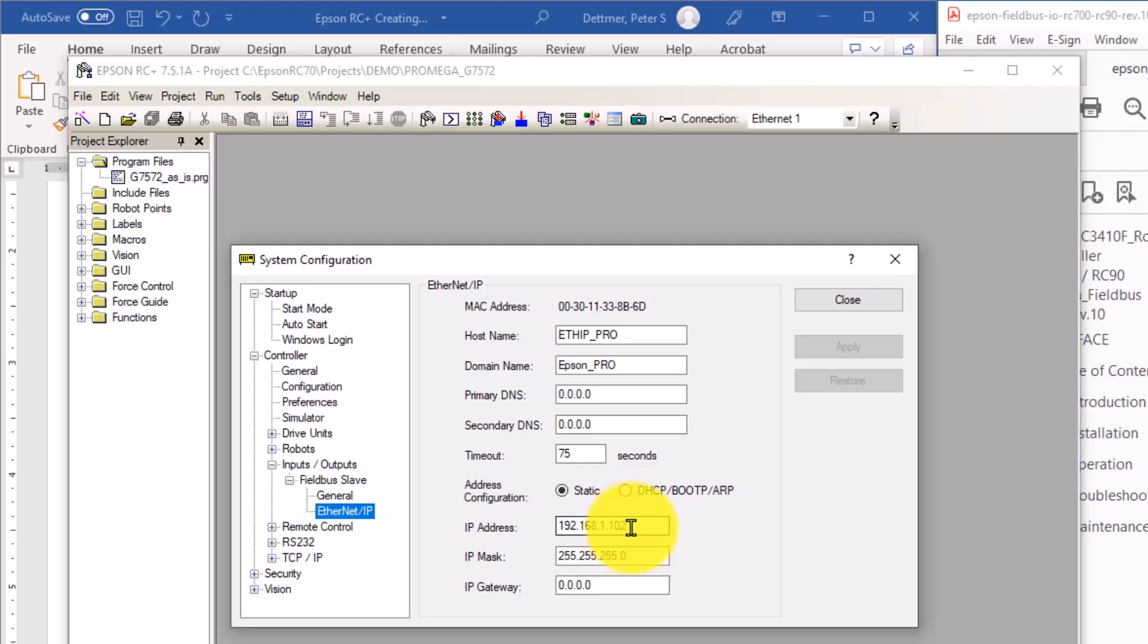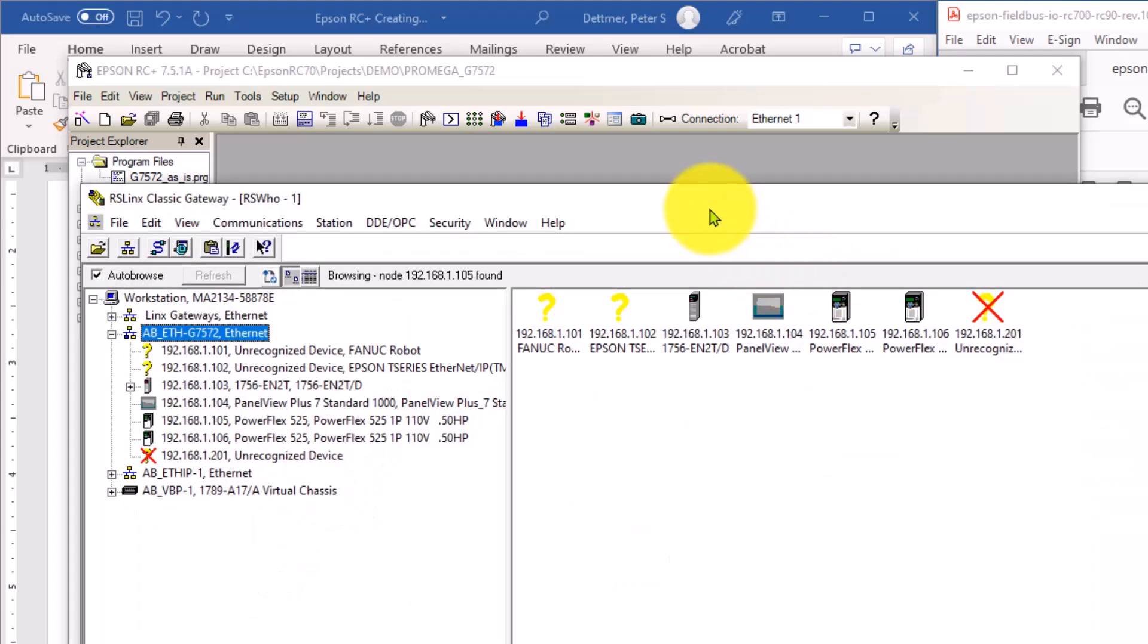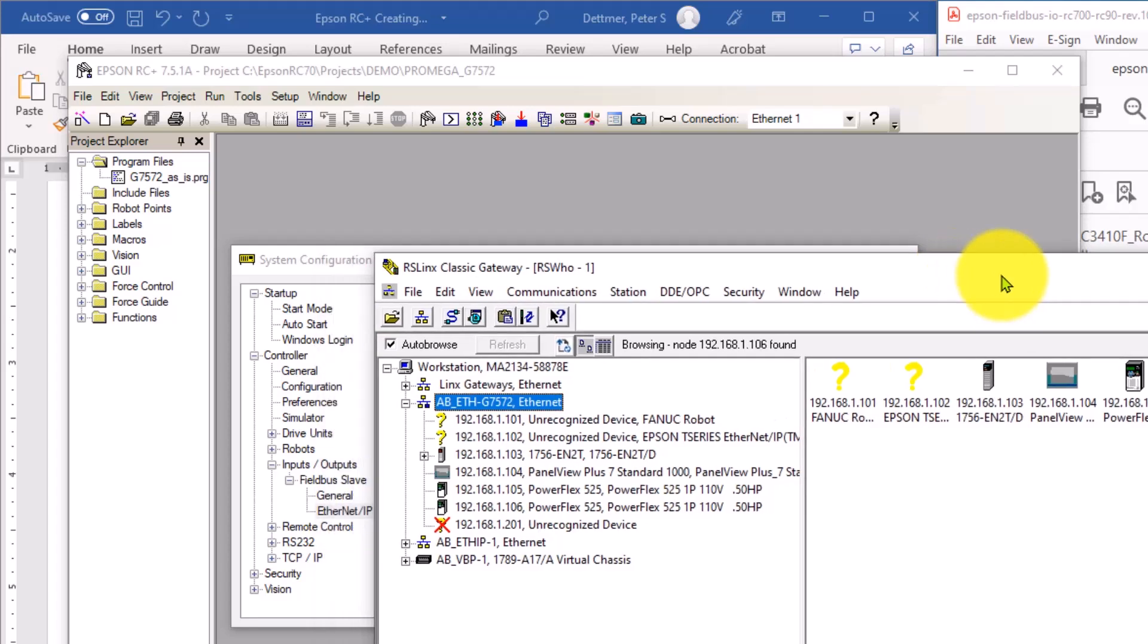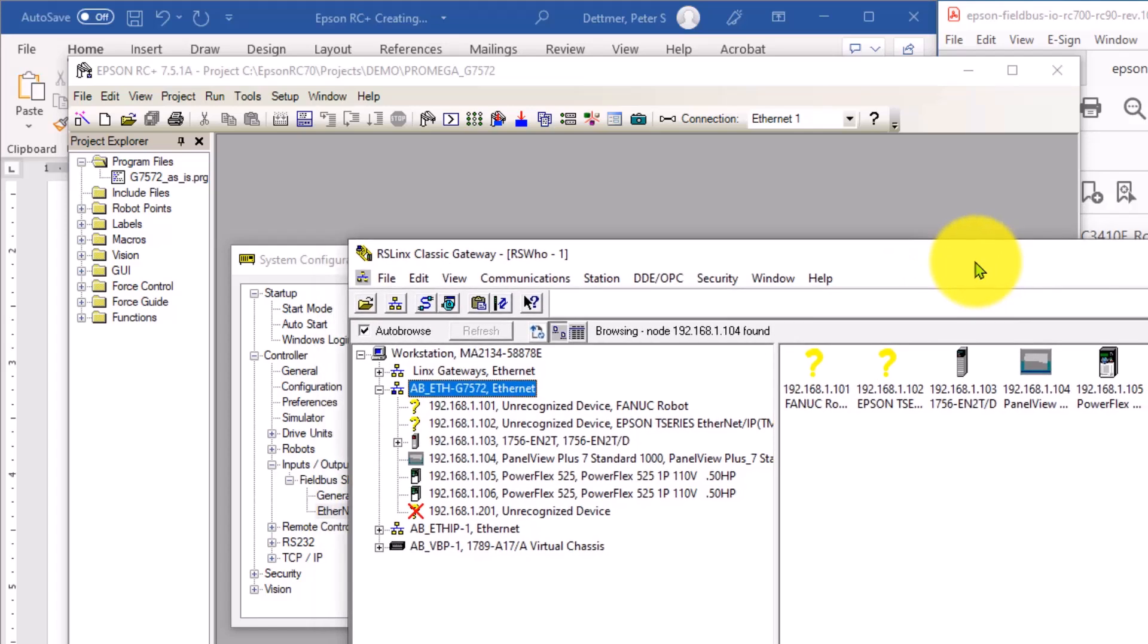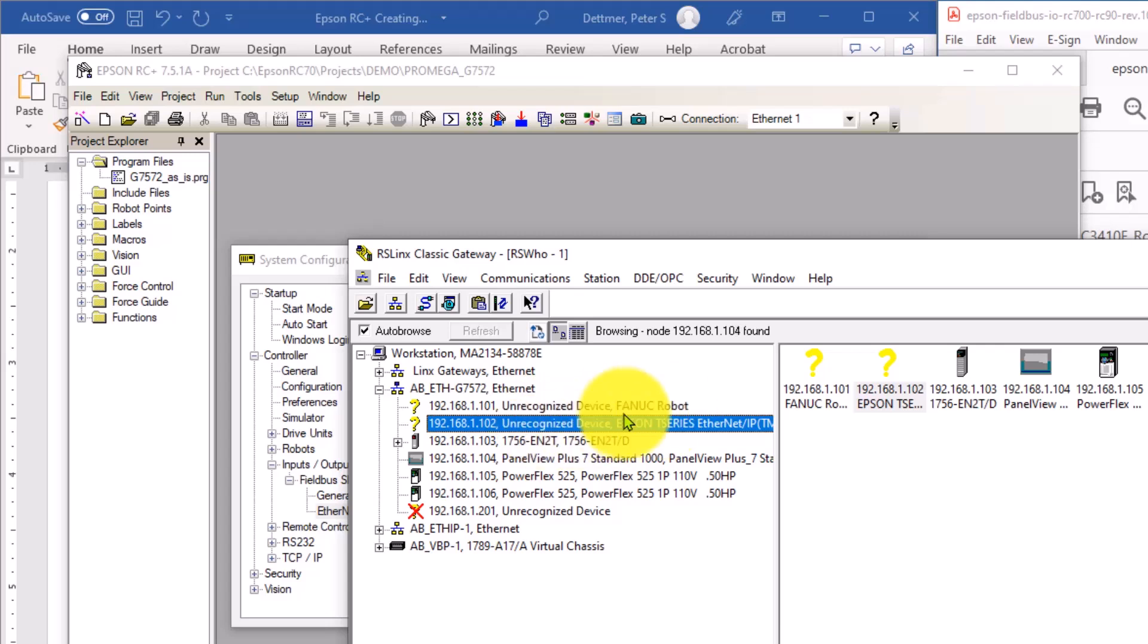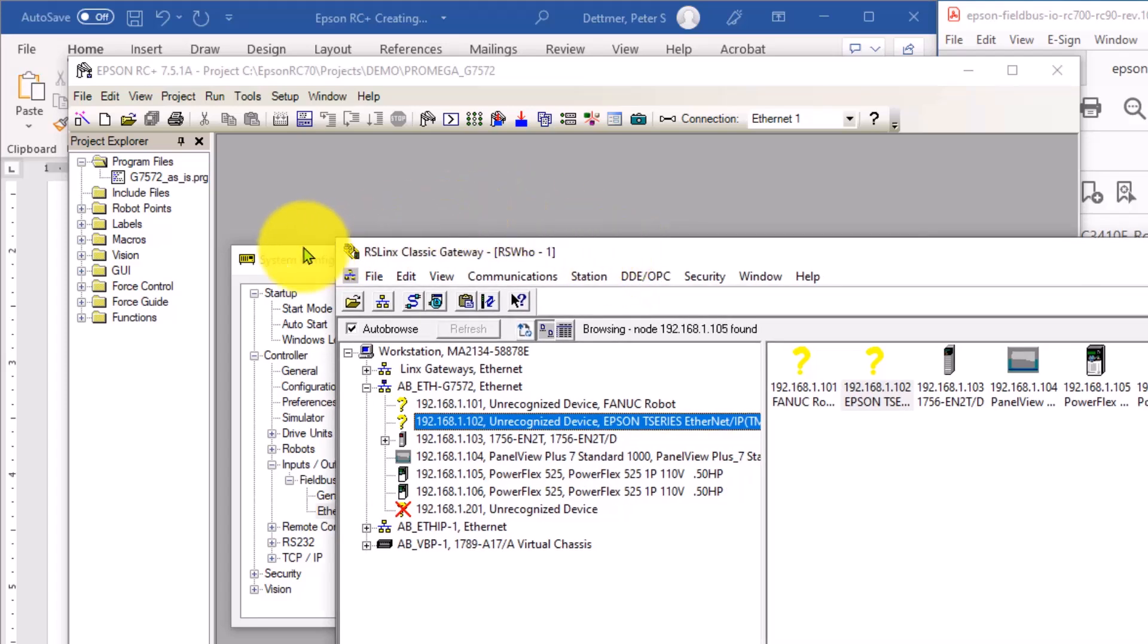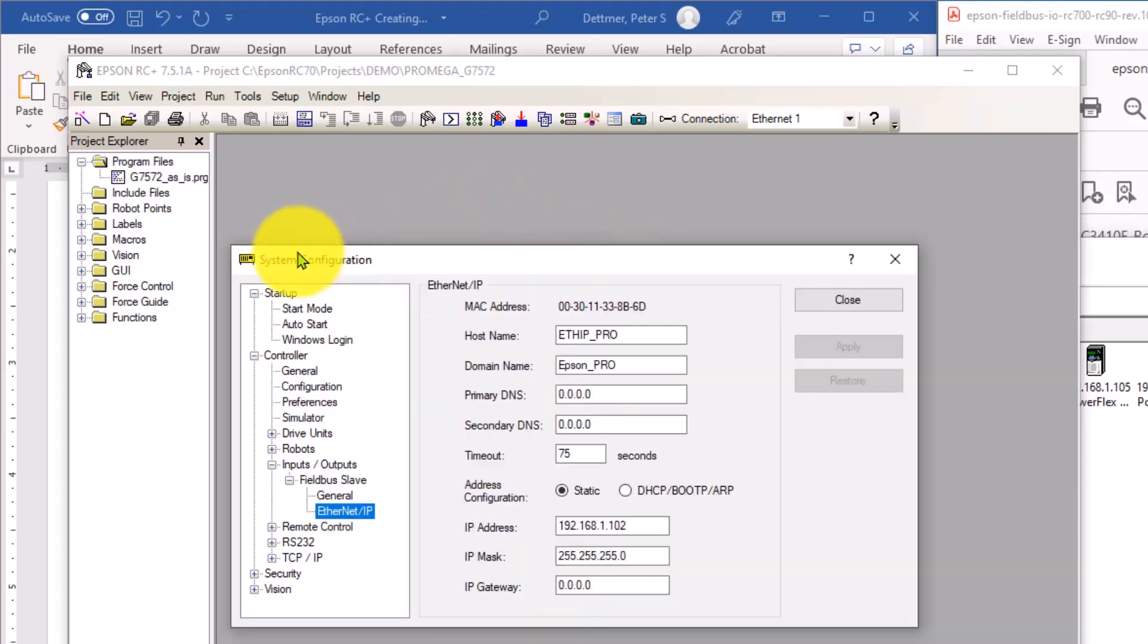And if you happen to have RSLogix 5000, RSLinx Classic Gateway set up, this is where you can see, this is the Ethernet connection that I'm using to communicate between my PLC and the robot, which is 102 in this case. So be sure that those are set up correctly and you don't have the same IP to both devices. That could lead to a lot of problems.